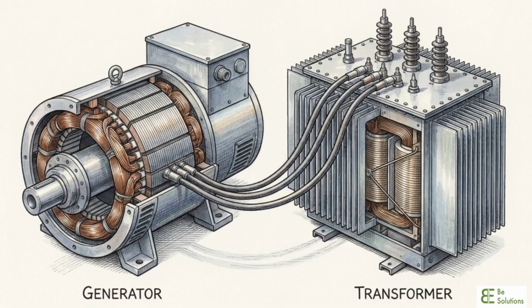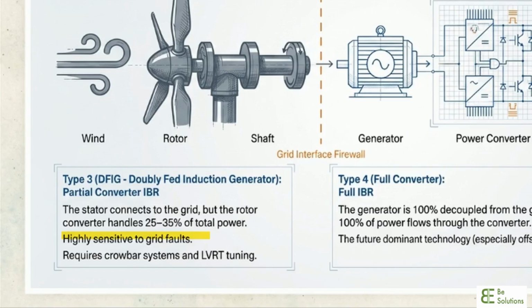Older Type 3 models, known as doubly fed induction generators, operate differently. Their stator connects directly to the grid, making them only partial IBRs. Because they lack a total electronic firewall, they are highly sensitive to grid faults. They require precise low-voltage ride-through software tuning and physical crowbar circuits to survive sudden voltage drops without destroying the machine.